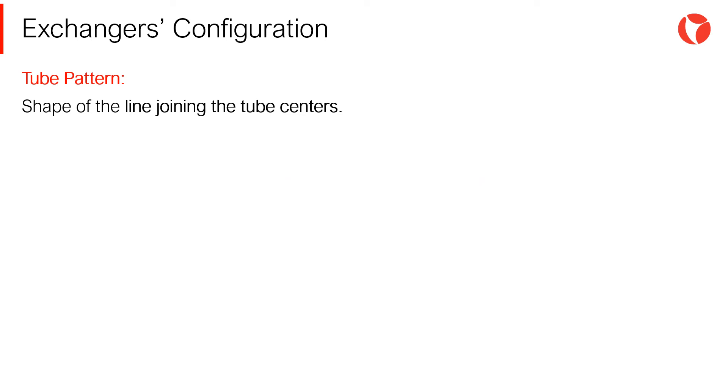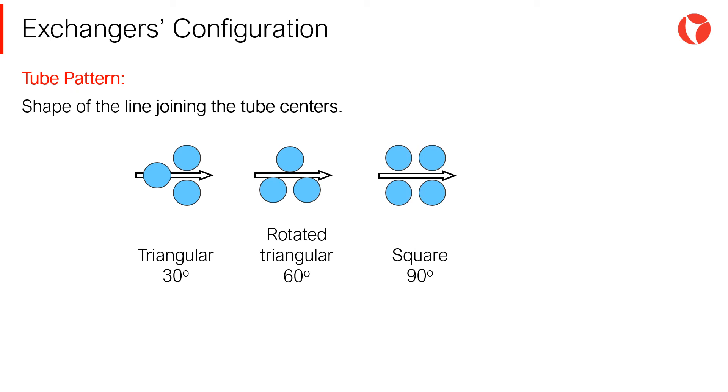The tube pattern is the shape presented by the line connected to the centers of the tubes, in a tube sheet cross section. Among other things, the tube pattern depends on the type of fluid in the shell and the velocity of this fluid. Both TEMA code and HEI standard establish that the permitted tube patterns are triangular 30 degrees, rotated triangular 60 degrees, square 90 degrees, and rotated square 45 degrees.